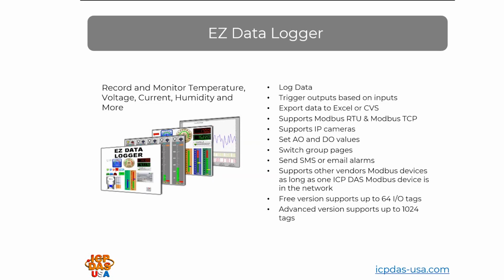It supports control logic, so you can configure it to trigger outputs based on input data, like the turning on of a fan based on a temperature level. You can also set up input fields, so you can set the analog output and digital output values. You can set them to open or close valves or to turn equipment on or off. You can use this with all sorts of different kinds of equipment that can communicate over Modbus, or you can use the signals that come from the data acquisition modules, like the 4 to 20 milliamps or the relay outputs, for example. Easy Data Logger stores data in a database, which can be exported for viewing in a spreadsheet.